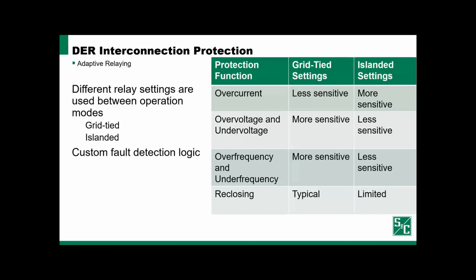Now, if we're looking at different settings groups or changing our settings to protect the system, there's a significant question that arises here. When are we going to switch between our settings groups, or when are we going to adjust the settings? Because if you're adjusting the settings, your protected device may be in an indeterminate state for some time while it's making those changes. And we want to ensure we're making that in an intelligent way to ensure the system is protected at all times.